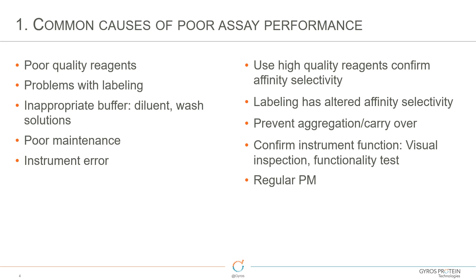We have several tools you can use: a visual inspection of the instrument, and a functionality test kit that can assess instrument function in ways that are challenging to inspect visually. Instrument errors can occur, and a regular PM visit by your service engineer will help mitigate problems with pumps, valves, or syringes. Having a regular PM where those components get swapped out is very helpful.